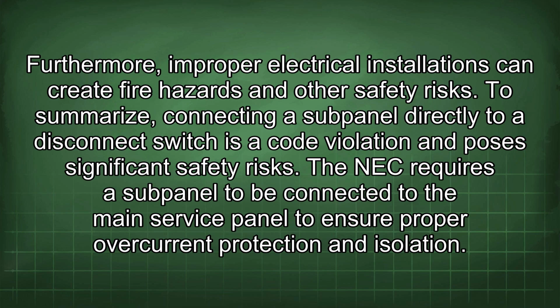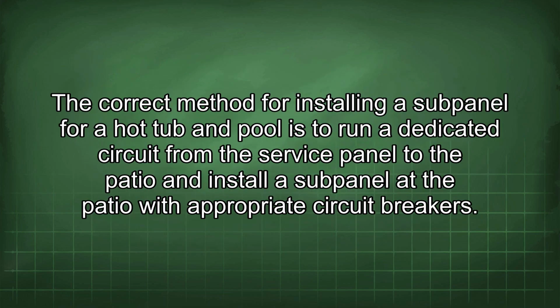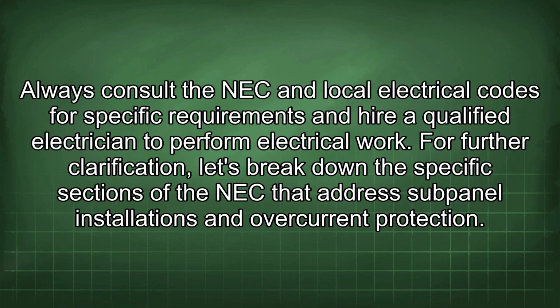To summarize, connecting a subpanel directly to a disconnect switch is a code violation and poses significant safety risks. The NEC requires a subpanel to be connected to the main service panel to ensure proper overcurrent protection and isolation. The correct method for installing a subpanel for a hot tub and pool is to run a dedicated circuit from the service panel to the patio and install a subpanel at the patio with appropriate circuit breakers. Always consult the NEC and local electrical codes for specific requirements and hire a qualified electrician to perform electrical work.